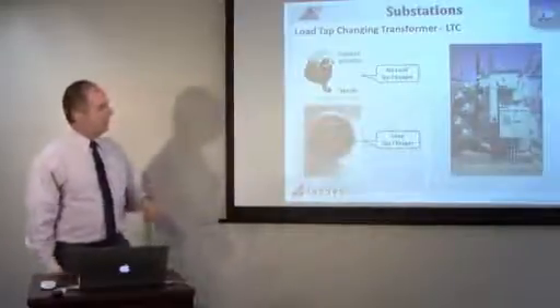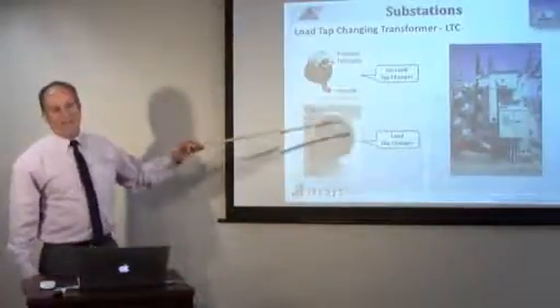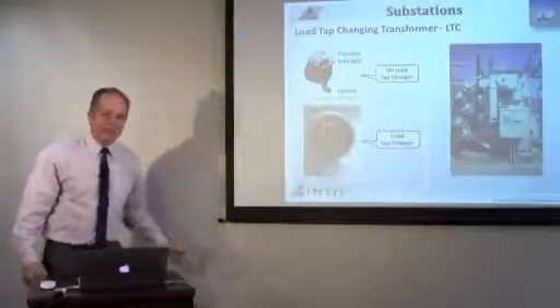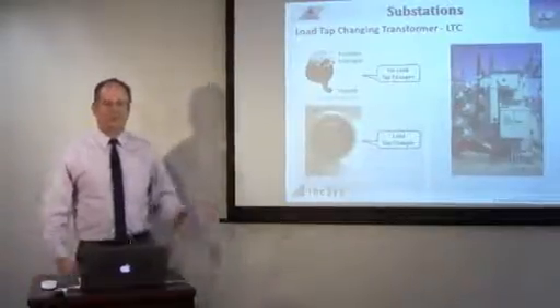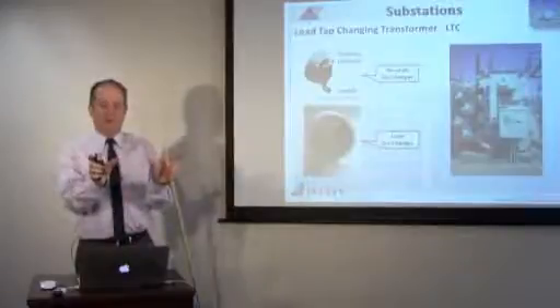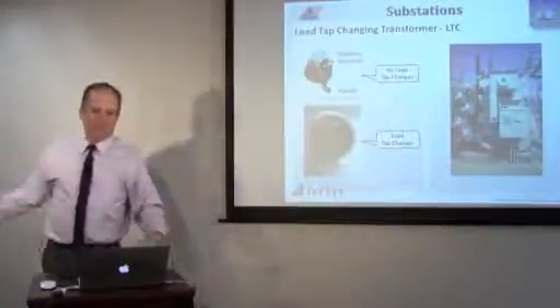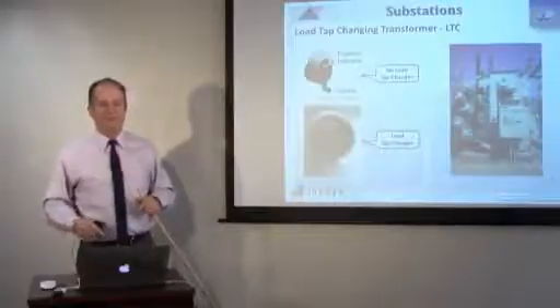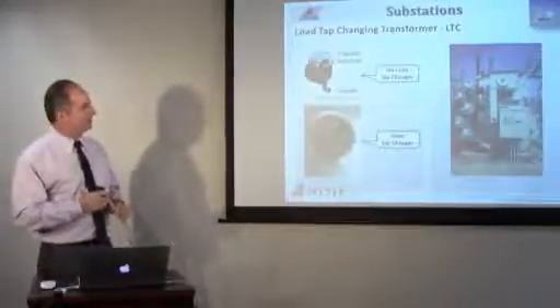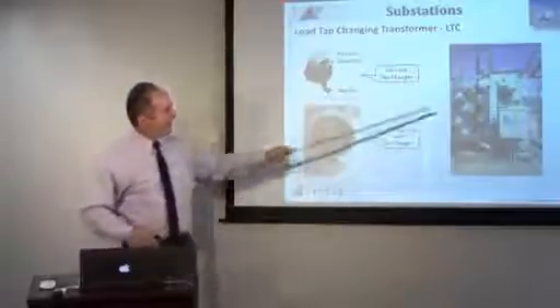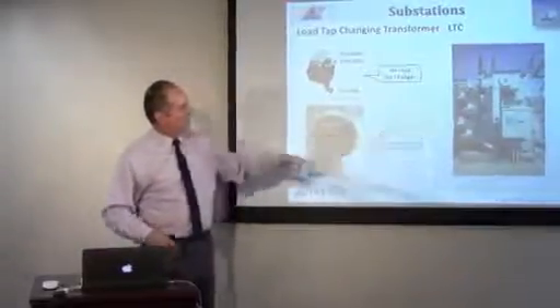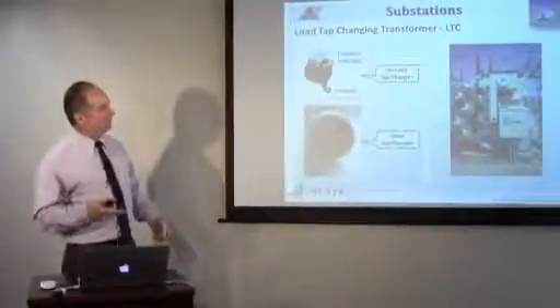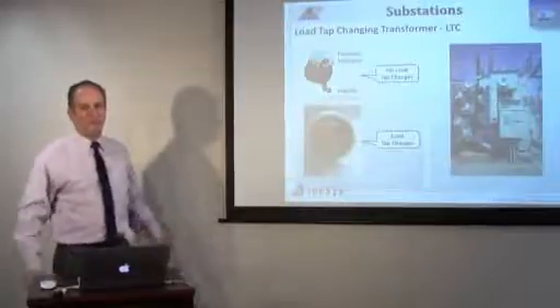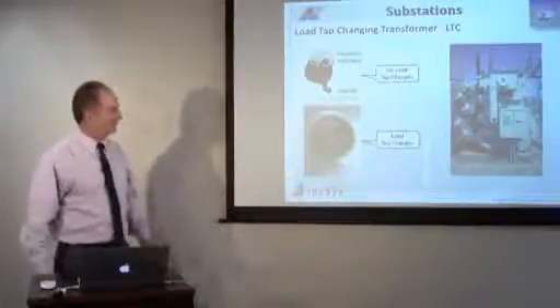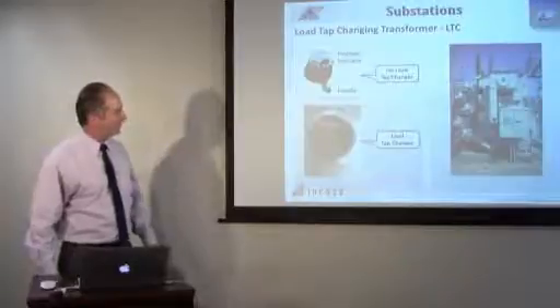A couple things about that. To do maintenance on the regulator, you've got to take the whole thing out of service, the whole LTC. So you have to have a substation that has 2 of them, or be able to take the load off and put on another transformer somewhere so you can de-energize that transformer and still have load or service to the other people. So, you know, they're advantageous that you have 1 unit instead of 2, but maintenance is still required, so you have to have at least 2 of those, you know, to make it really economical.